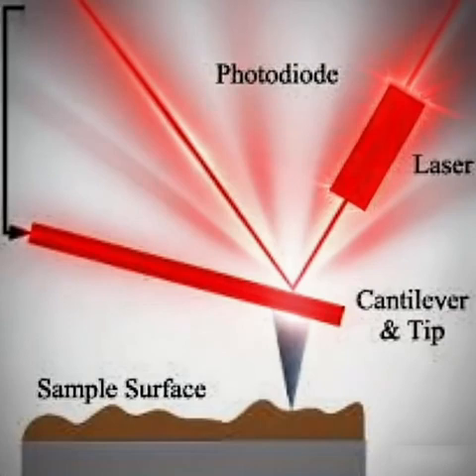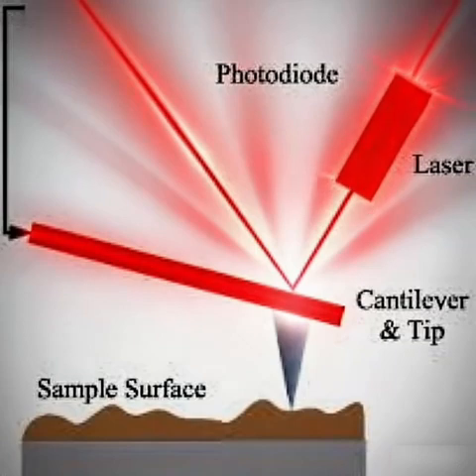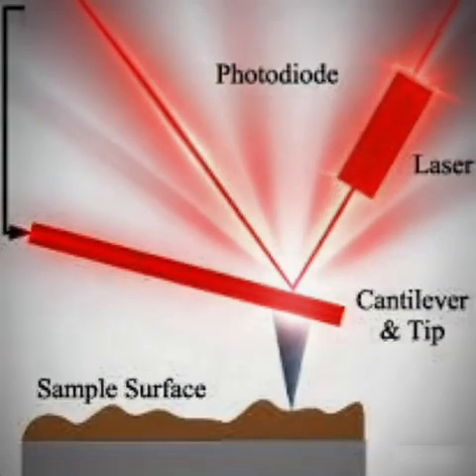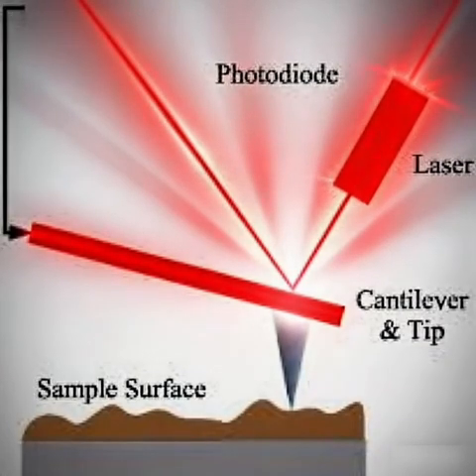What about heat? That's a huge issue in chips, too. Oh, absolutely. So on the thermal side, we have crucial modes too. Scanning thermal microscopy, STHM, is about finding the heat signatures. It detects changes in heat conduction or just the local temperature between that probe and the sample. This allows for detailed analysis of heat transfer, finding local thermal defects, or pinpointing hotspots, areas getting unusually warm, which could indicate an impending failure, overheating. Finding the hot spots. Precisely.